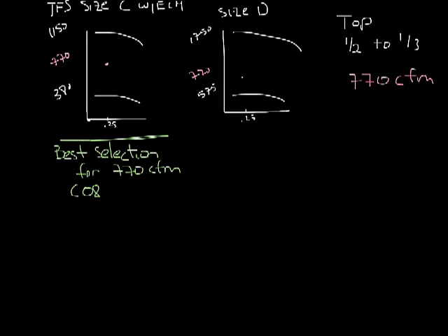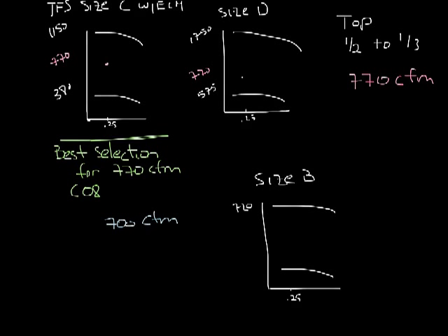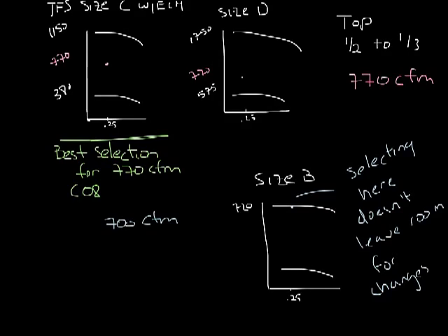Now if you needed 700 CFM, there would actually be three possible unit casing sizes that would work, because the size B TFS with the ECM motor has a fan curve that has a maximum at 720 CFM at 0.25 inches. But in this case, you would be right at the top of the fan curve. Selecting here doesn't give you much leeway in case the pressures are higher than expected, or your airflow requirements change.